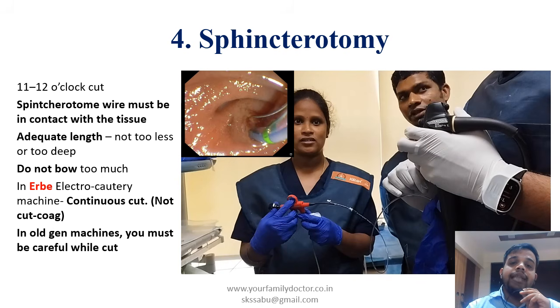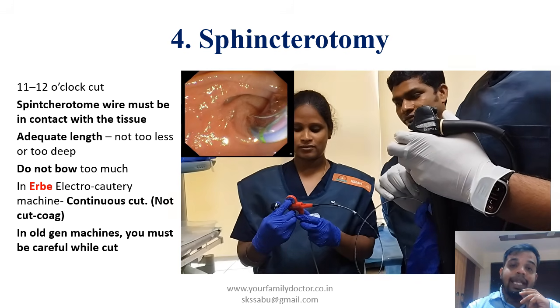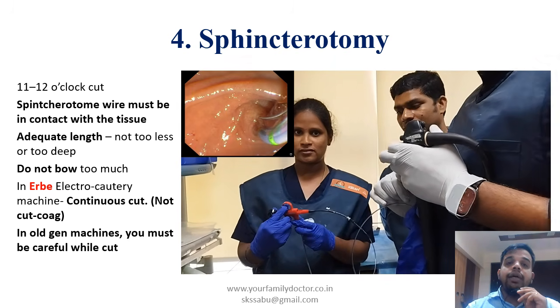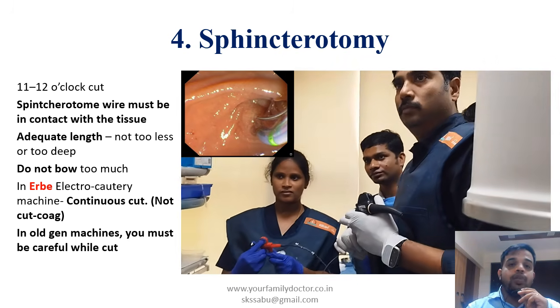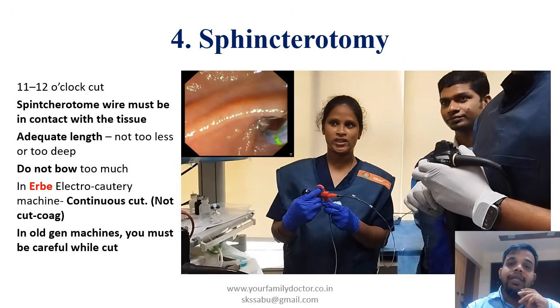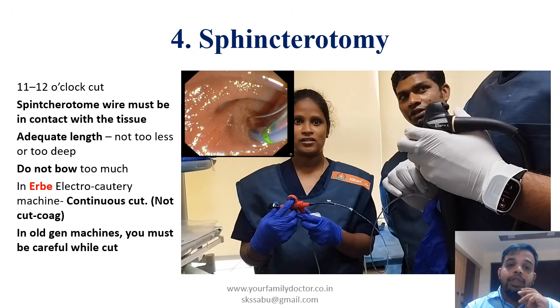The most important thing is the yellow pedal, or the cut pedal, which you should continuously press. You should not do cut, coagulate, or cut, release. You should not do that. You just continuously press the yellow pedal. The machine will automatically process it and do the cycles of cut, coagulate, and pause.